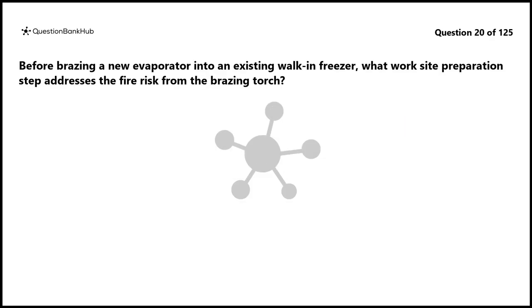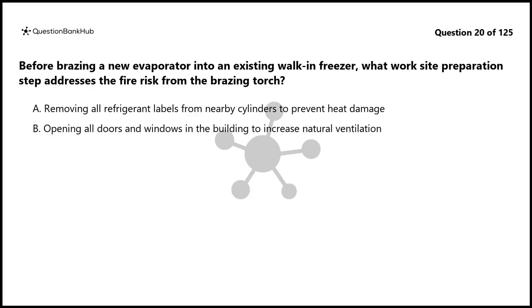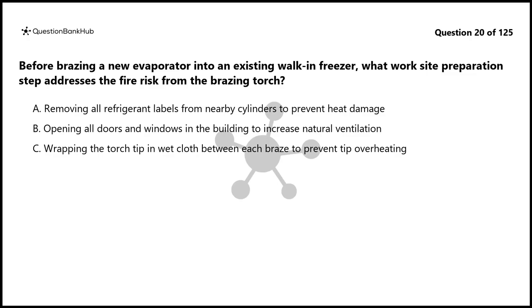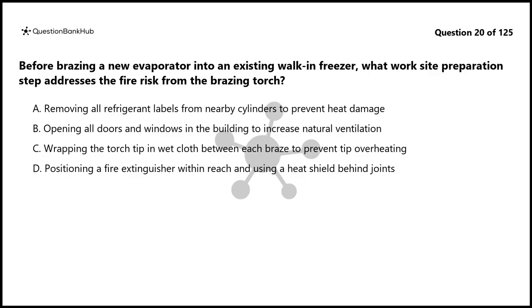Question 20. Before brazing a new evaporator into an existing walk-in freezer, what work site preparation step addresses the fire risk from the brazing torch? A. Removing all refrigerant labels from nearby cylinders to prevent heat damage. B. Opening all doors and windows in the building to increase natural ventilation. C. Wrapping the torch tip in wet cloth between each braze to prevent tip overheating. D. Positioning a fire extinguisher within reach and using a heat shield behind joints.